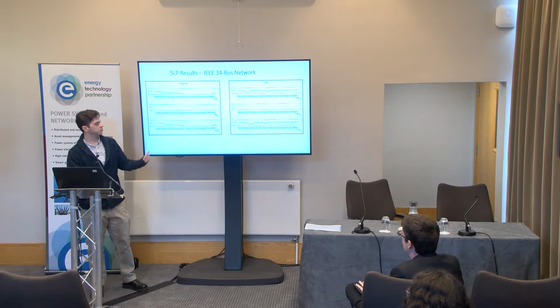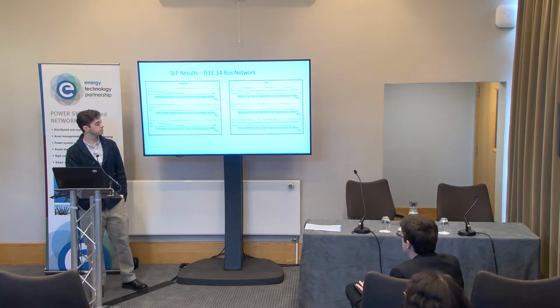For example, for the 34-bus network, there's the substation transformer, and there's also 2 spots where it has voltage regulators in the default model. So for my test for this one, I took the substation transformer, I took the 2 voltage regulator spots, and replaced them with hybrid transformer models.